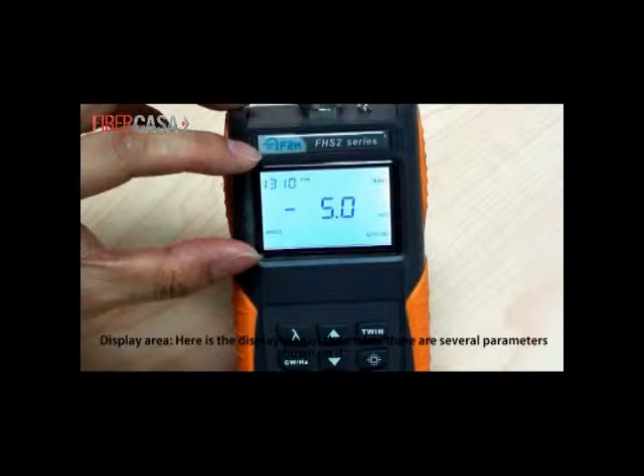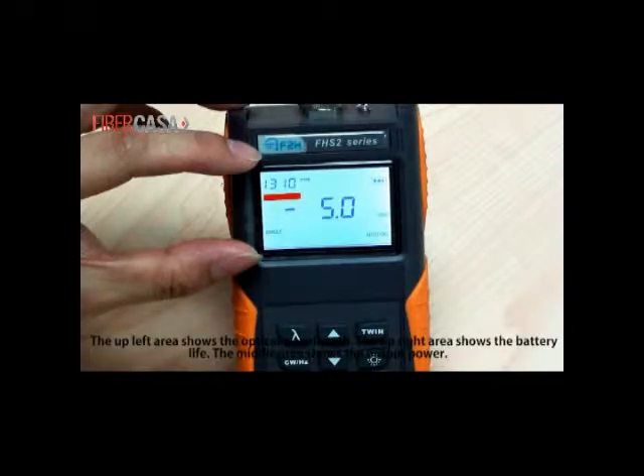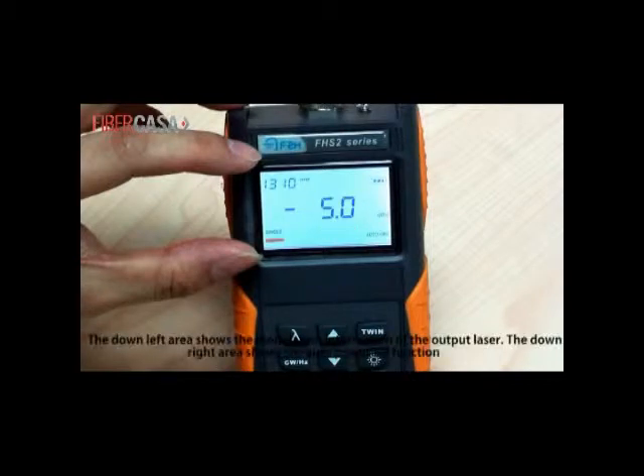Display Area. Here is the display area of the meter. There are several parameters shown on it. The upper left area shows the optical wavelength. The upper right area shows the battery life. The middle area shows the output power. The down left area shows the modulation information of the output laser. The down right area shows the auto power off function.